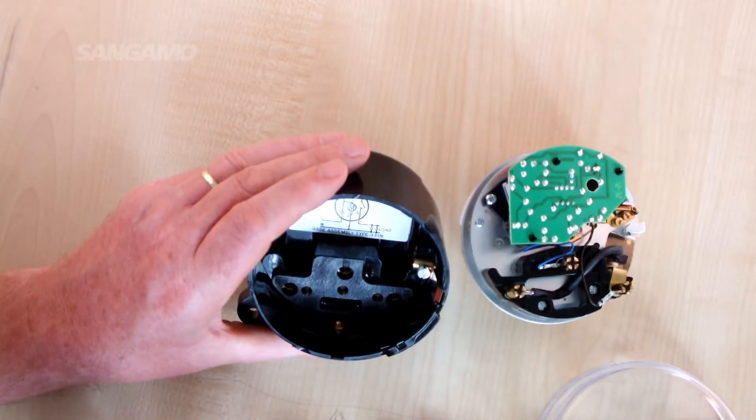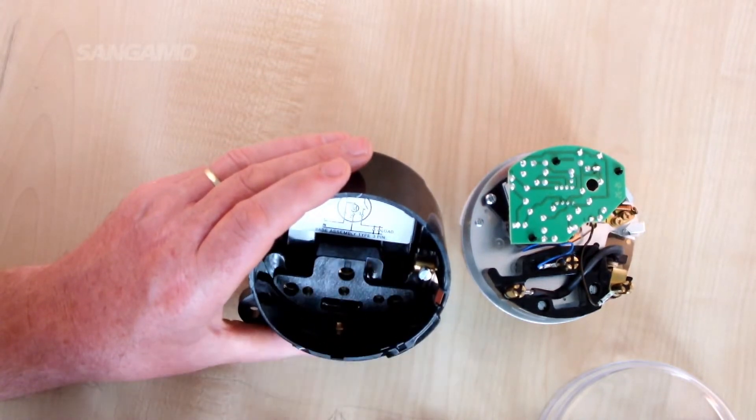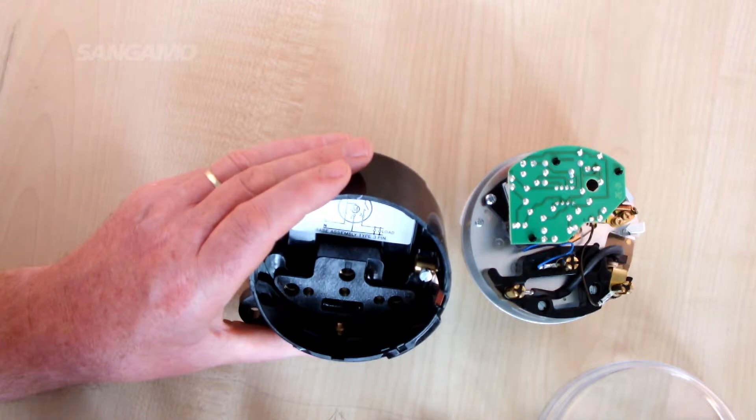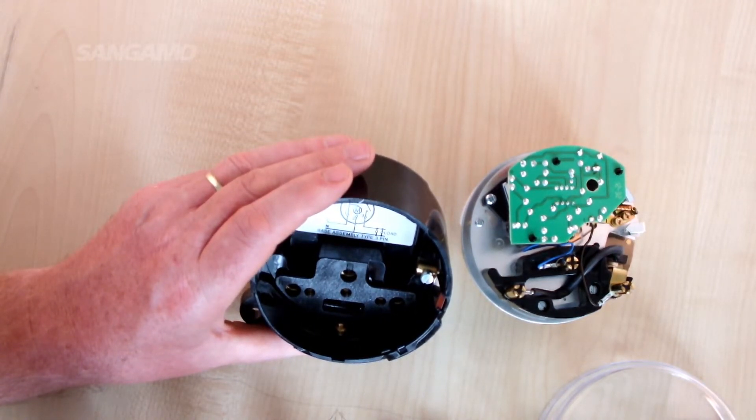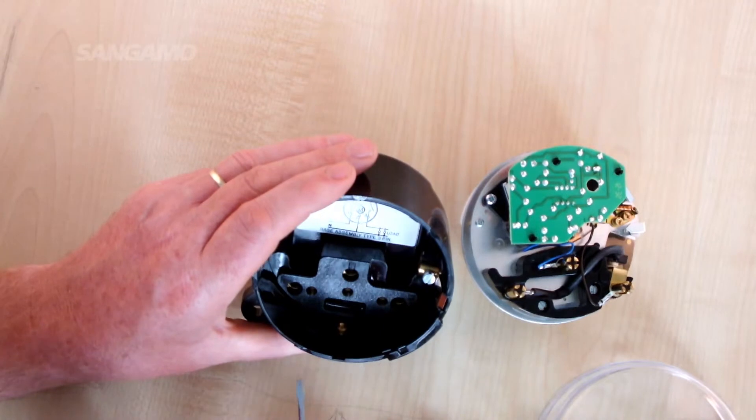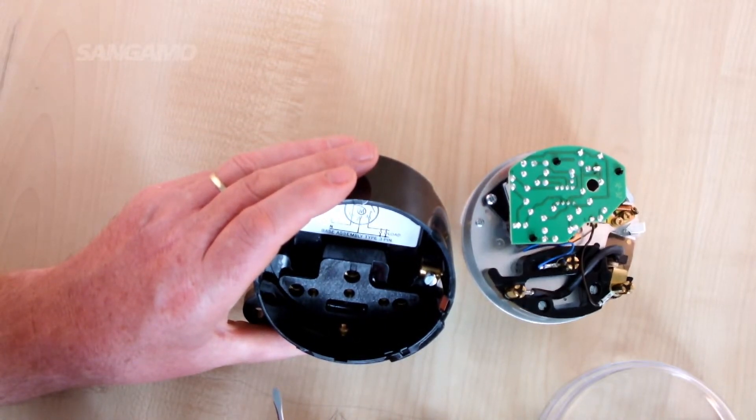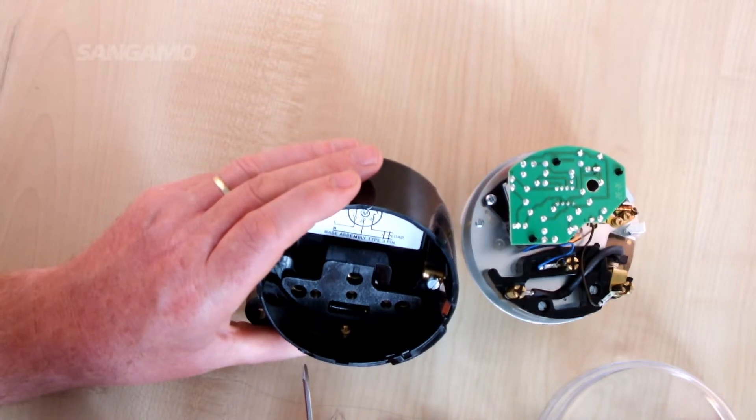You then make the electrical connections as per the wiring diagram shown in the base. The time switch is intended for fixed wiring only, and provision must be made for a means of disconnection from the supply with a contact separation of 3mm on all poles. For more details on the wiring of individual terminals, go to our other how-to video.